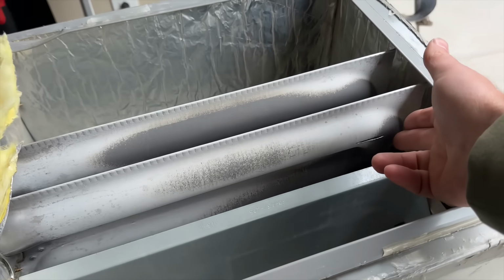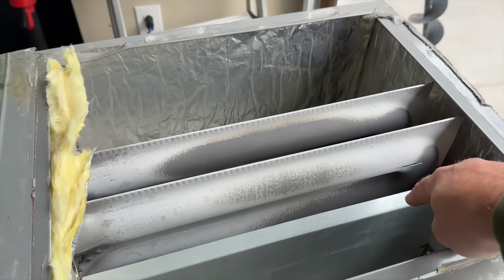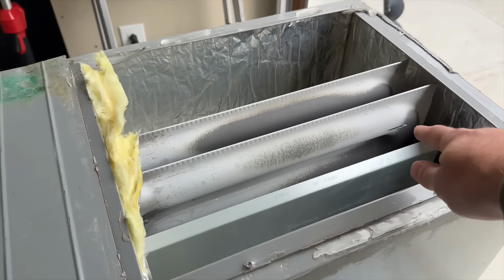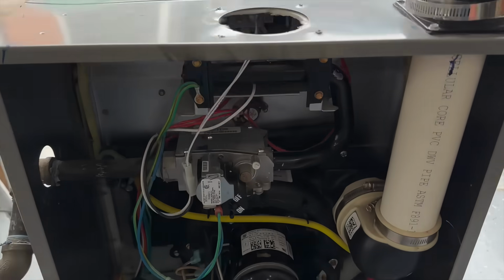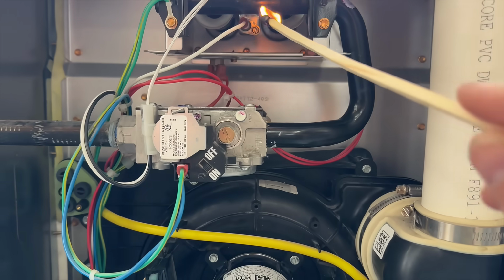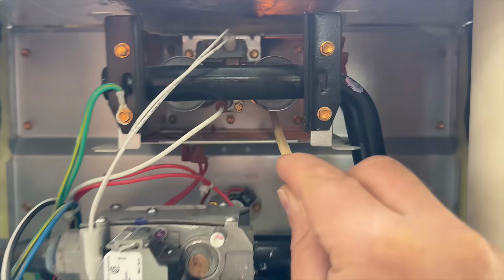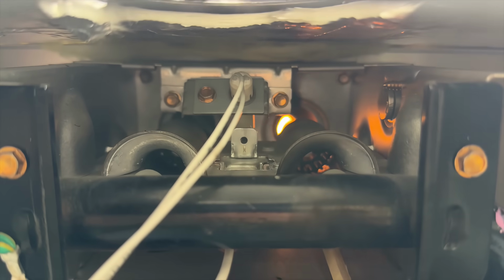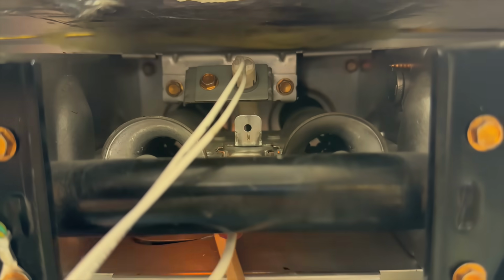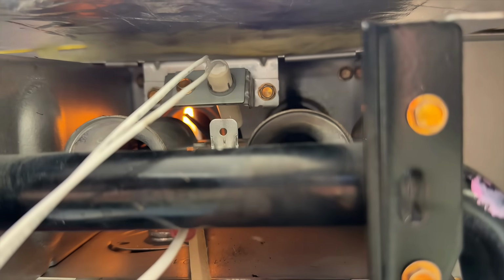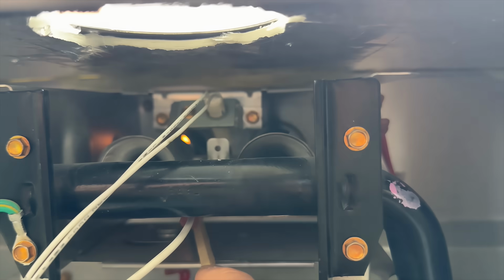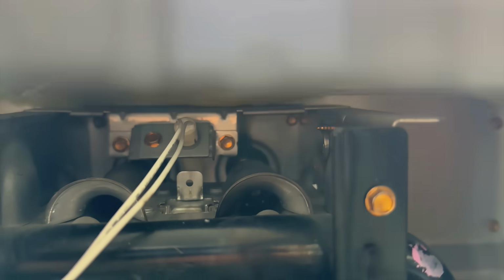All right, so we've created a decent sized crack in the heat exchanger. That's typically where they end up, is on these bends here. So we've created a little incision there, and we're basically just gonna redo these two tests. Okay, so now that we have the hole in the heat exchanger, check this out. So when we put it over to here, notice how that flame is just dancing all over the place. But watch this, when I put it in the other one, straight up and down. So that conclusively tells if you have a crack in your heat exchanger. See how that's fluttering around? That's exactly what you'll see if you have a crack in the heat exchanger.